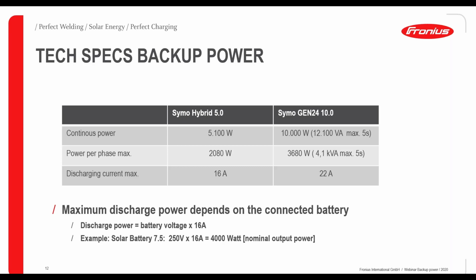The maximum discharging power depends also on the connected battery. So you need to multiply the battery voltage with the amperage. For example, a solar battery with 7.5 has got a battery voltage of 250 volts. Multiplied with 16 amps gives a 4 kilowatt nominal output power from discharging in backup power mode. So basically, the battery modules usually have about 50 volts, also with BYD. When you use a bigger battery with 8 modules, you have a voltage of about 400 volts. That's also important to know, because with that you have a higher discharging power as well, and you can get more energy whenever you use the system in backup power mode.